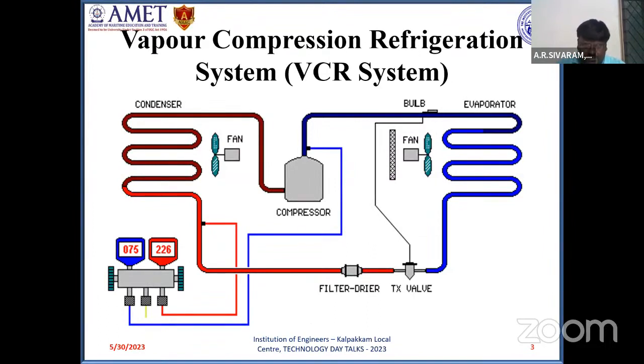This is an outline of a vapor compression refrigeration system. Normally, it has four major components: a compressor, a condenser, a metering device which controls the flow of refrigerant, and an evaporator. In the compressor, the working fluid, that is the refrigerant, gets compressed and leaves at high pressure and high temperature to the condenser. In the condenser, the refrigerant undergoes condensation from vapor to liquid, and the high pressure liquid then enters the metering device and undergoes expansion. Its temperature and pressure get reduced, and finally it extracts heat in the indoor unit, that is the evaporator, and enters the compressor again as a vapor, and the cyclic process continues.